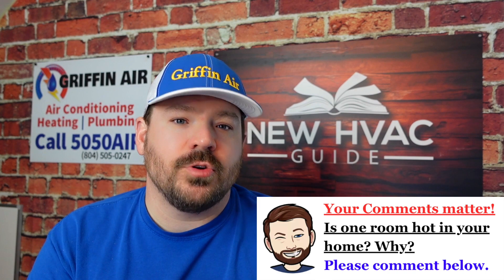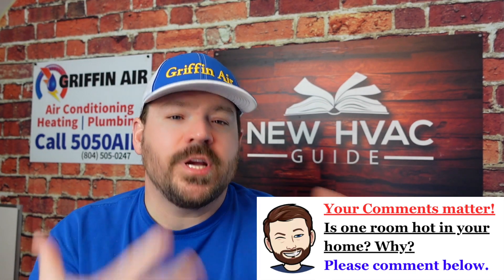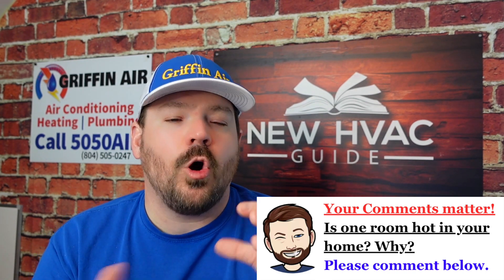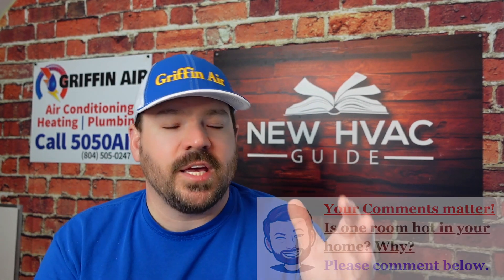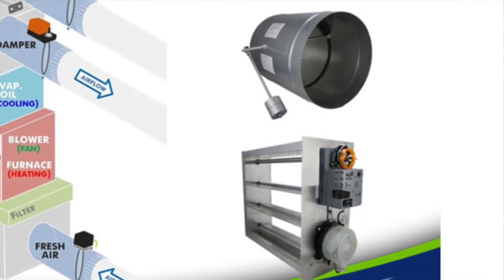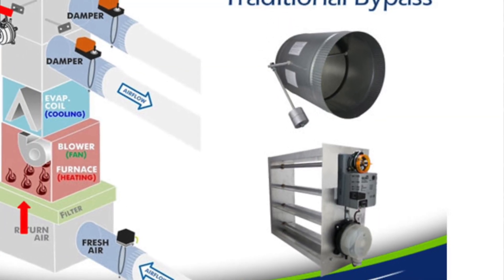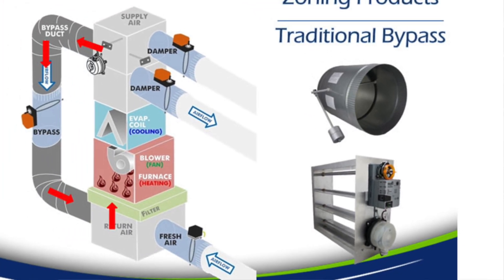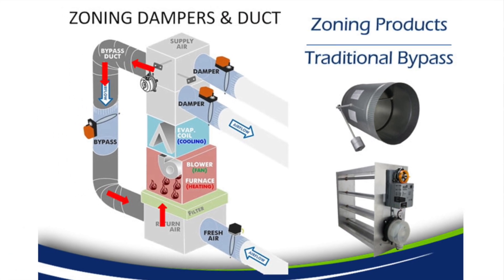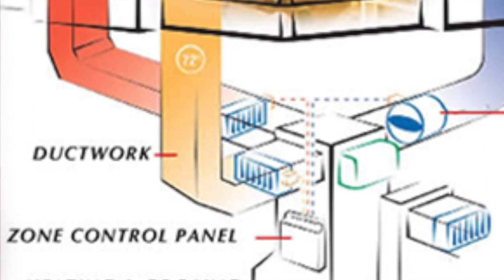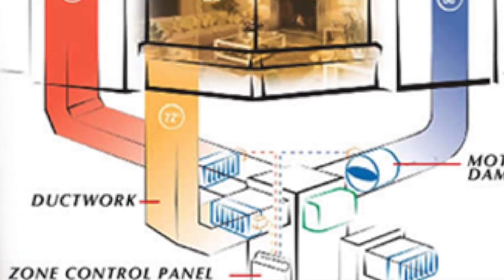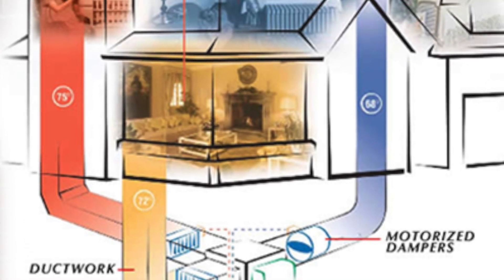Because it's a zoning issue, it needs to be treated as such — as a whole separate zone. You can do things like install dampers on the ductwork with another thermostat, have those dampers continue to dump more air in there when it's appropriate, when the rest of the system turns off, and you treat it as a zoning problem. You can also do things like add a mini split — I've seen folks do that in certain situations to try to fix a zoning problem.